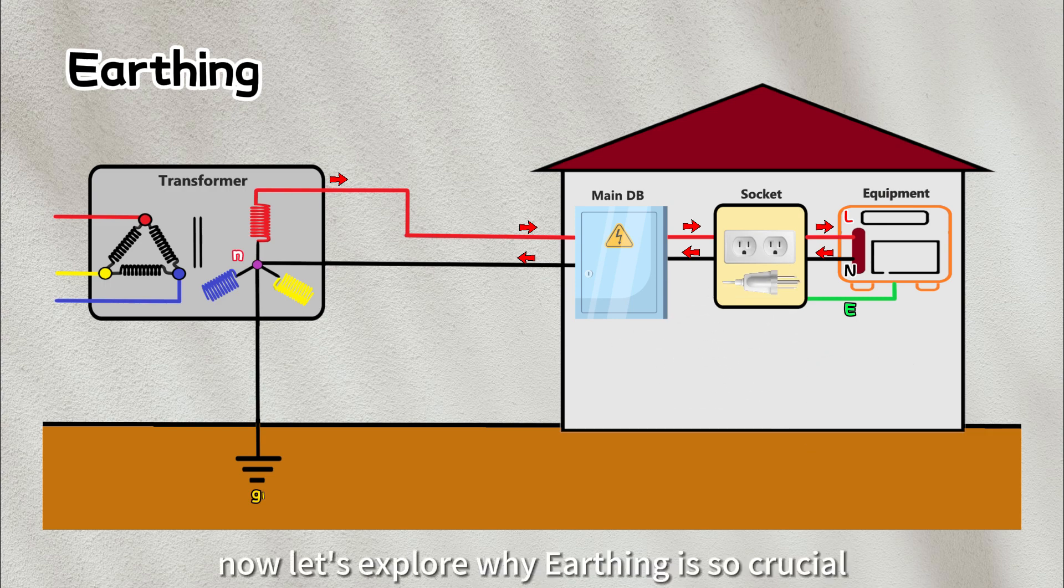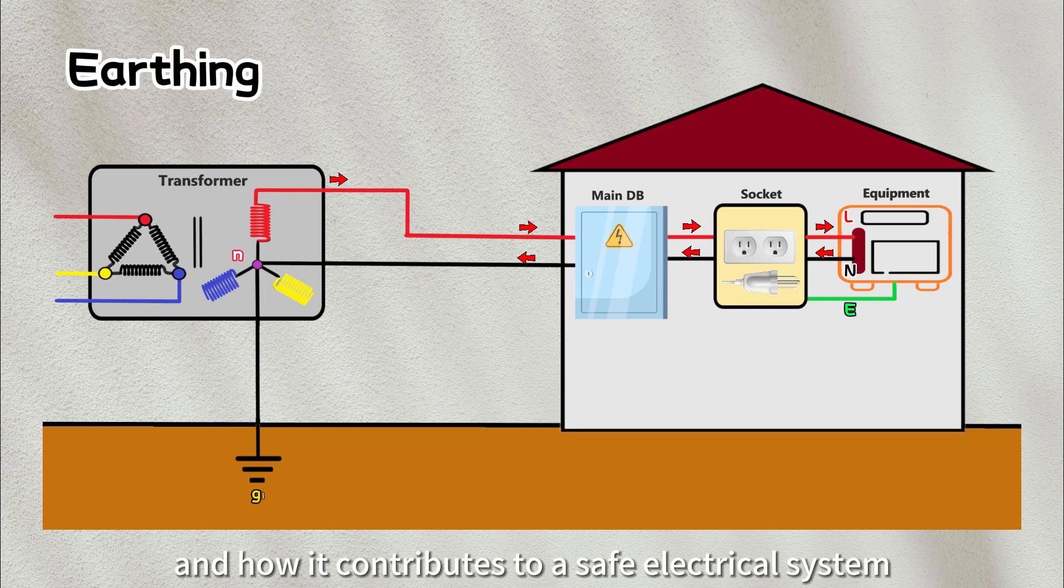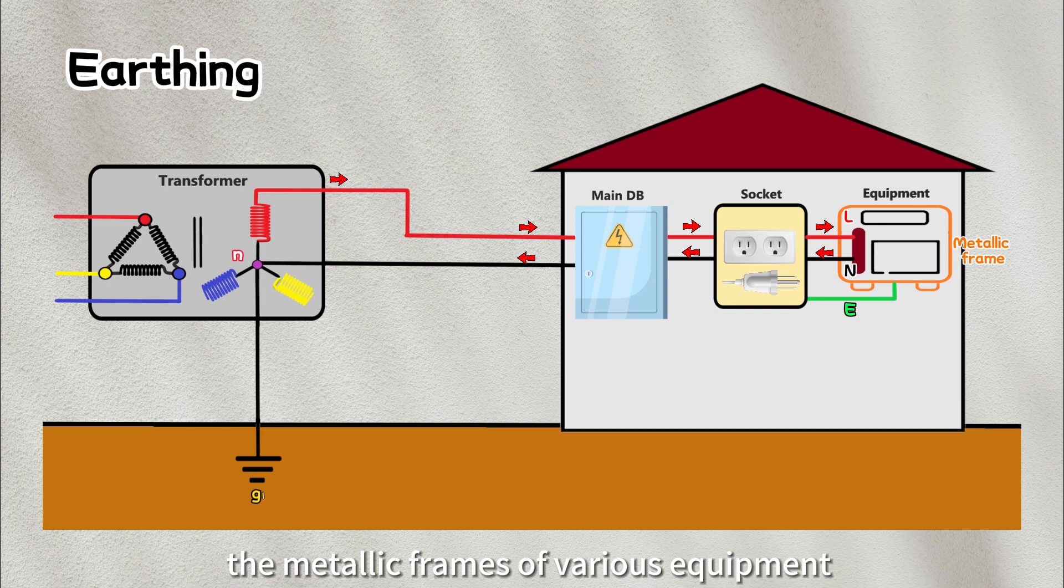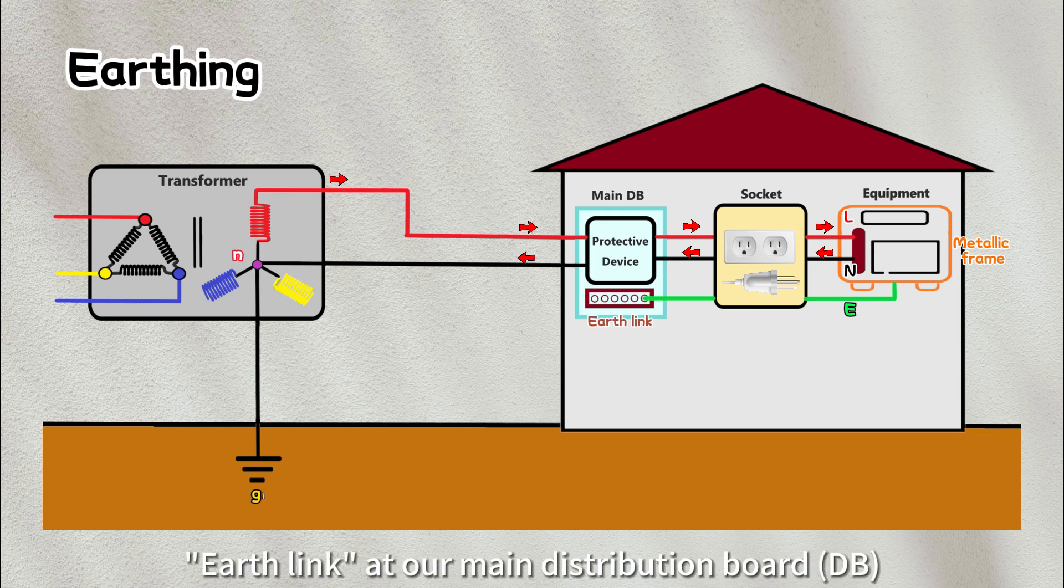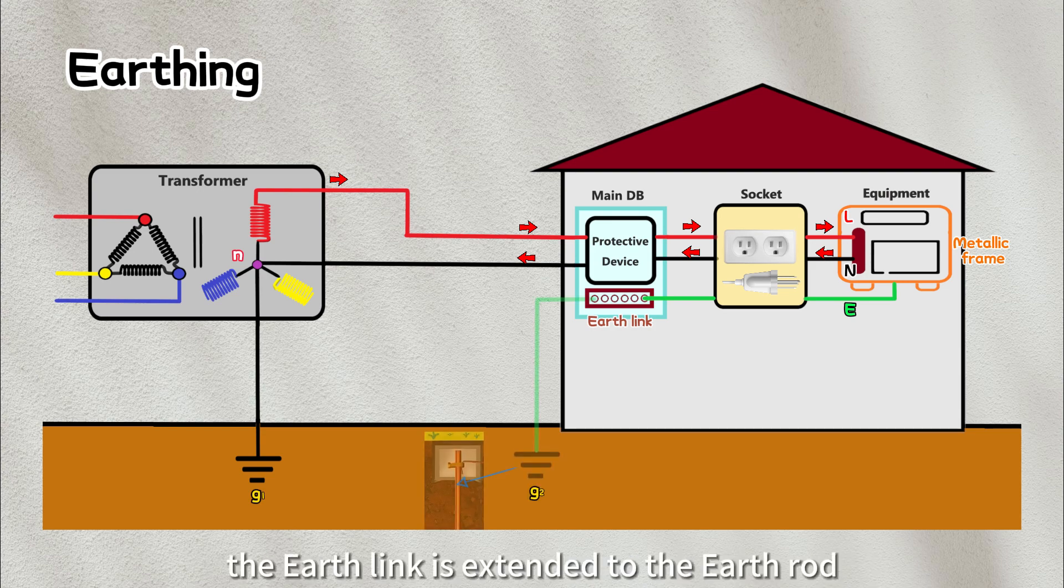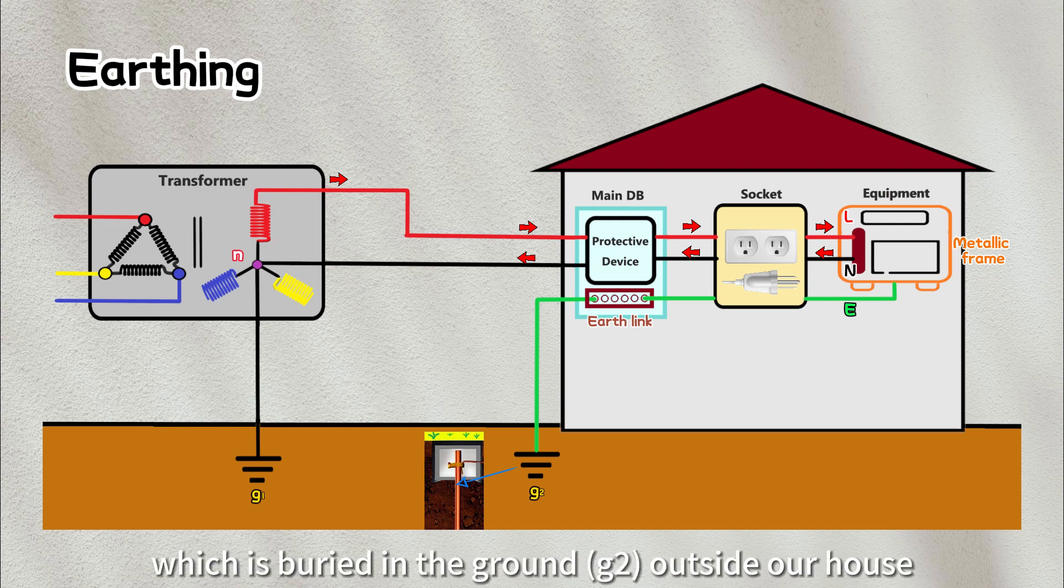All right, now let's explore why earthing is so crucial and how it contributes to a safe electrical system. In practical applications, the metallic frames of various equipment are commonly connected to the earth wire. Subsequently, all these earth wires are connected to the earth link at our main distribution board. From there, the earth link is extended to the earth rod, which is buried in the ground outside our house.